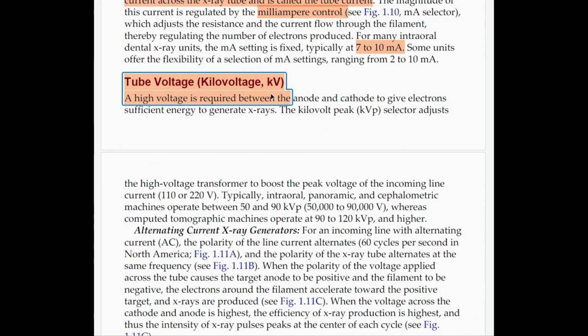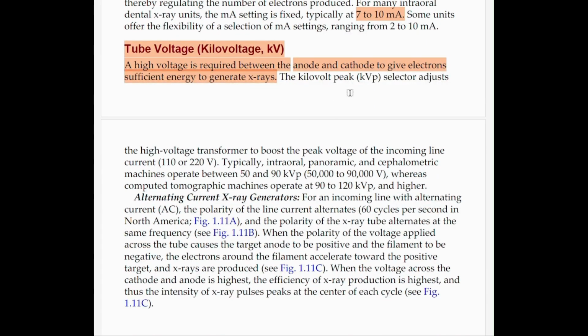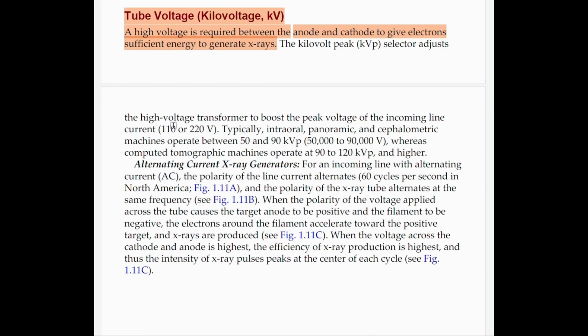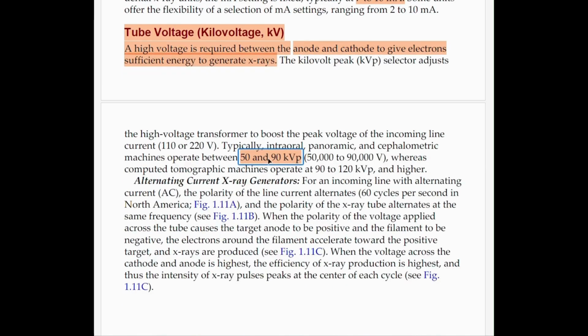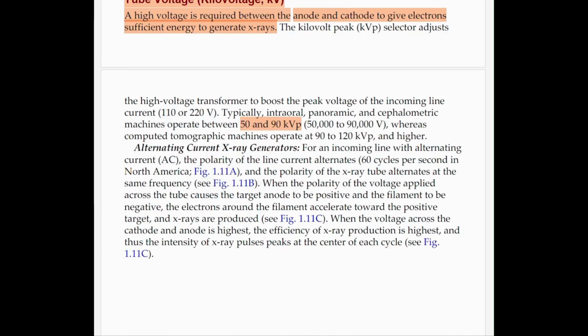Next, we move on to tube voltage. High voltage is required between the anode and the cathode to give electrons sufficient energy to generate the X-rays. The kilovolt kVp selector adjusts the high voltage transformer to boost the peak voltage of the incoming line current. Typically, intraoral, panoramic and cephalometric machines operate between 50 to 90 kVp. Once again, the values are important: 7 to 10 milliamperes, 50 to 90 kVp.